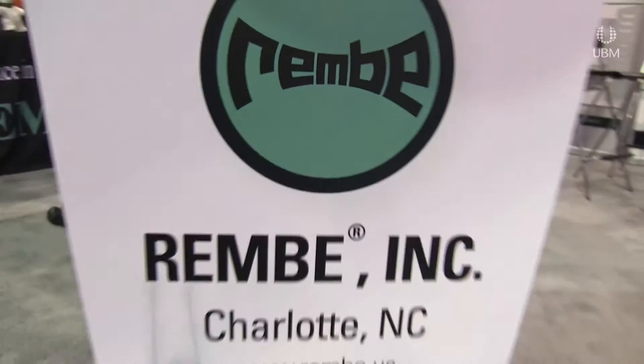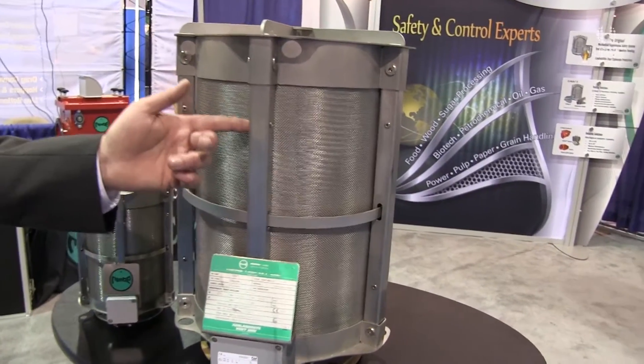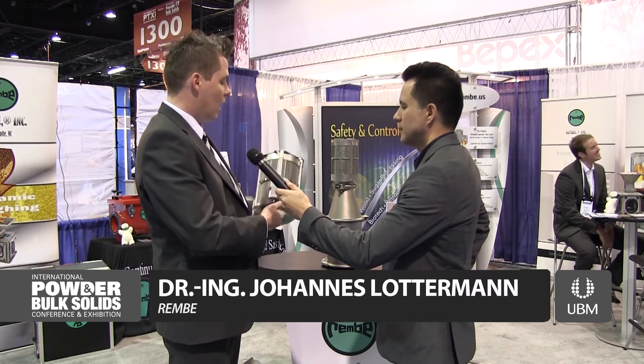If a company is interested in this type of product — it is not that easy to build, as you can imagine. The Q-Rohr technology was invented in the 80s by the founder of the company Rembe, Mr. Bernhard Penno, in collaboration with Dr. Alfred, and we improved the technology over the years. For the U.S. market, the Q-Rohr flameless venting technology is approved by FM, standardized in FM standard 7730. In the European market and other markets, we follow the EN 16009 standard for flameless venting devices.